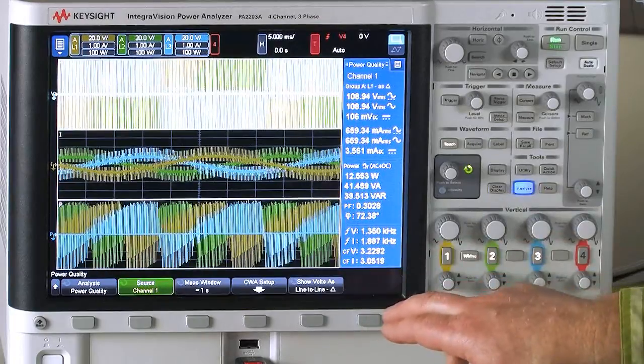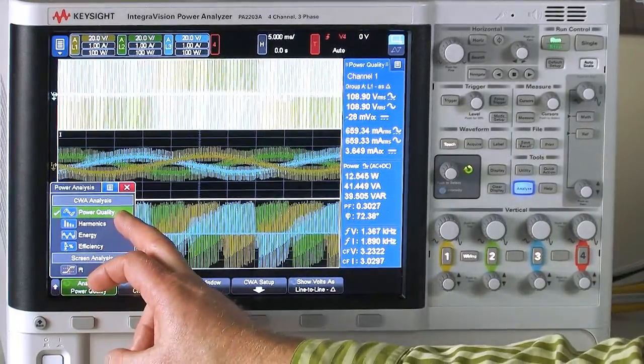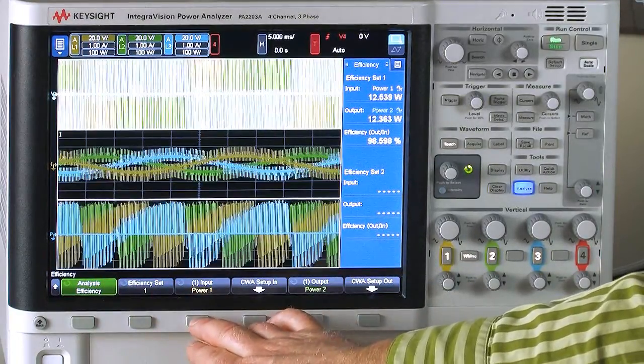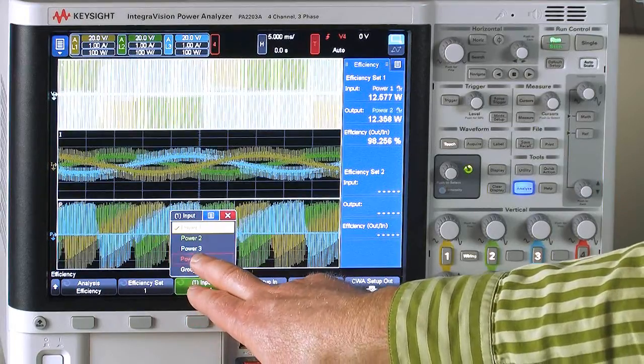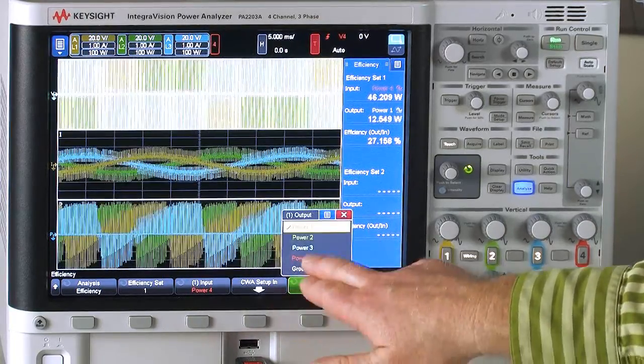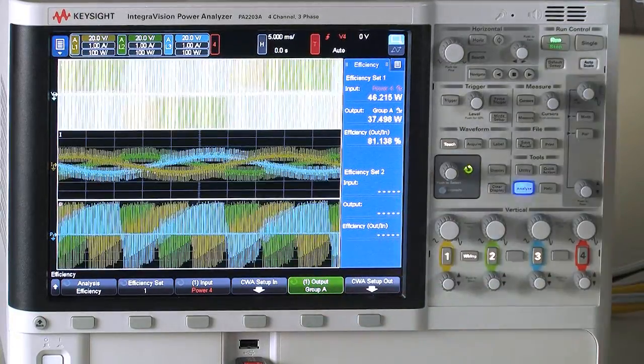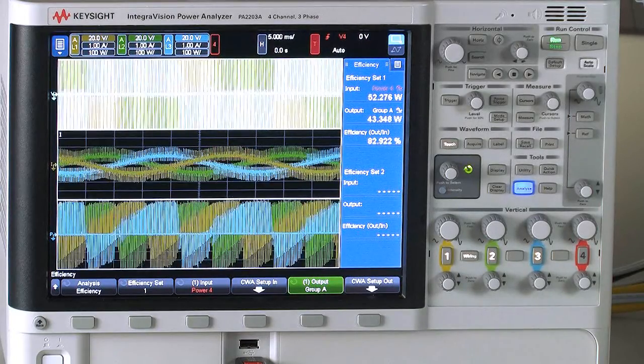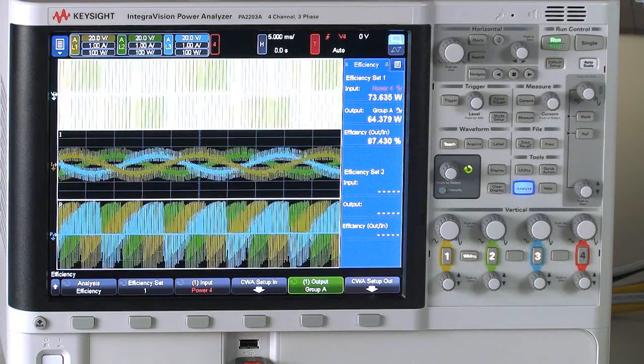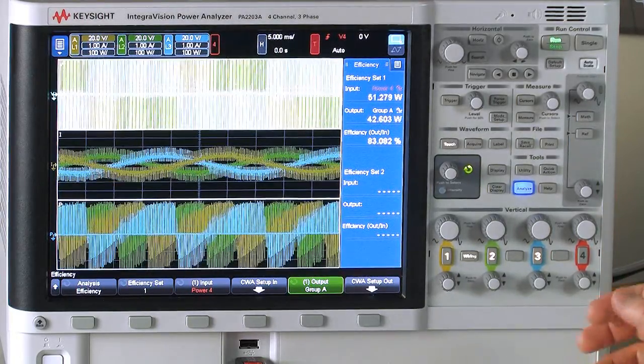There's other analysis features that we can actually do here. Right now it's looking at power quality. We can also look at the efficiency of the VFD from the input to the output. And so I can define my input power as power number four because that's my line in and my output power as the grouped three phase power. And I can see the actual efficiency that this is running at. I can vary the speed of this thing. It runs at 80% efficiency at slow speeds. And as I increase the speed, the efficiency of this thing goes up. So it's just one of the measures that you can make is looking at efficiency input to output on a VFD.